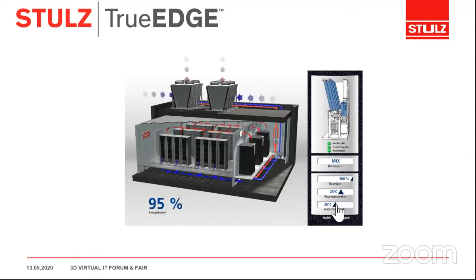So we can use, for example, the mix mode. We've got a second heat exchanger inside, using the outside temperature through the dry cooler to save money. So now we're using mix mode, both heat exchangers, the evaporator and the water-glycol mixture. The lower the temperature, the less the energy consumption. Here it's free cooling, only the heat exchanger is running, no compressor, and the compressor consumes lots of energy.